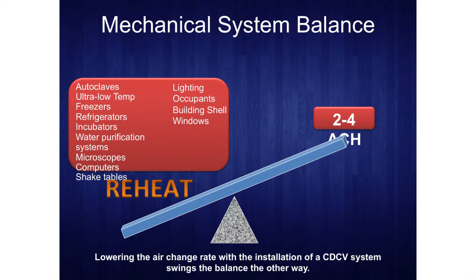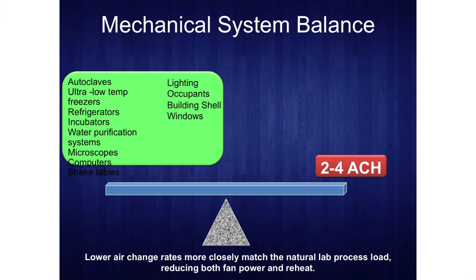What we really want is that balance. So where is that balance? Where is the balance of all this equipment in the lab, plus my skin load, plus my lighting load, and where does that balance out with a supply air temperature in the 55 to 60 degree range? 2 to 4 air changes per hour. How do I know that?